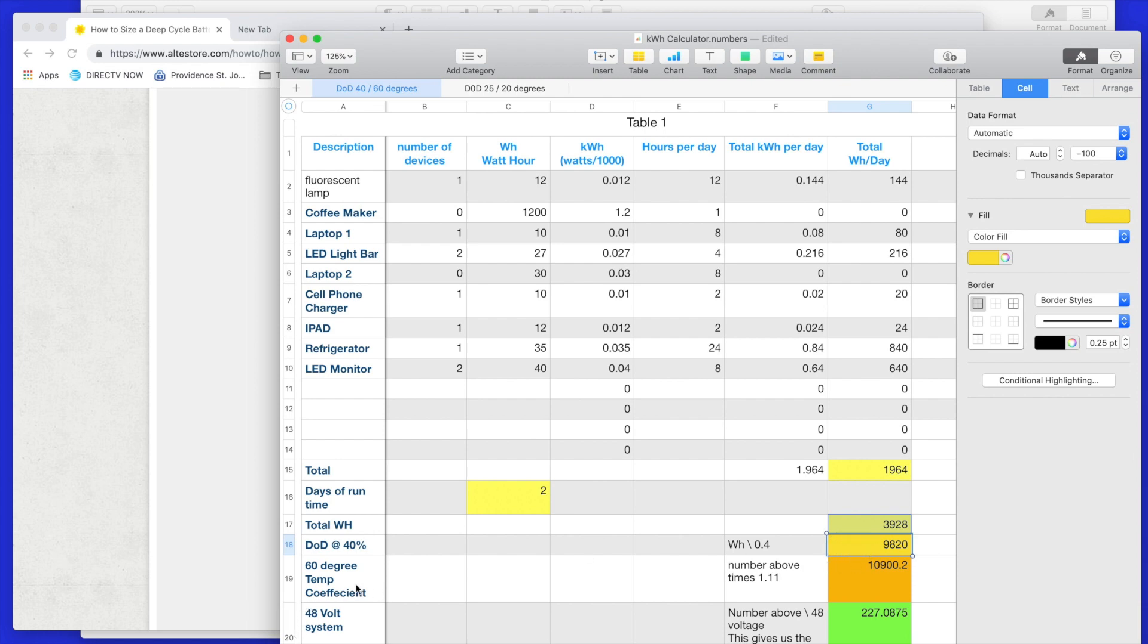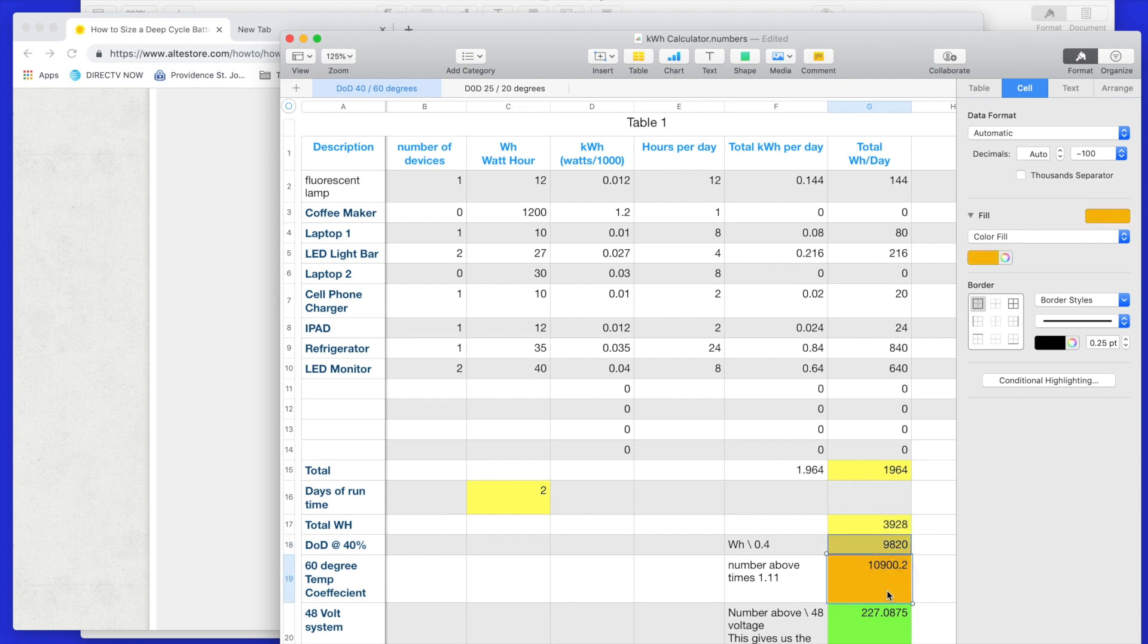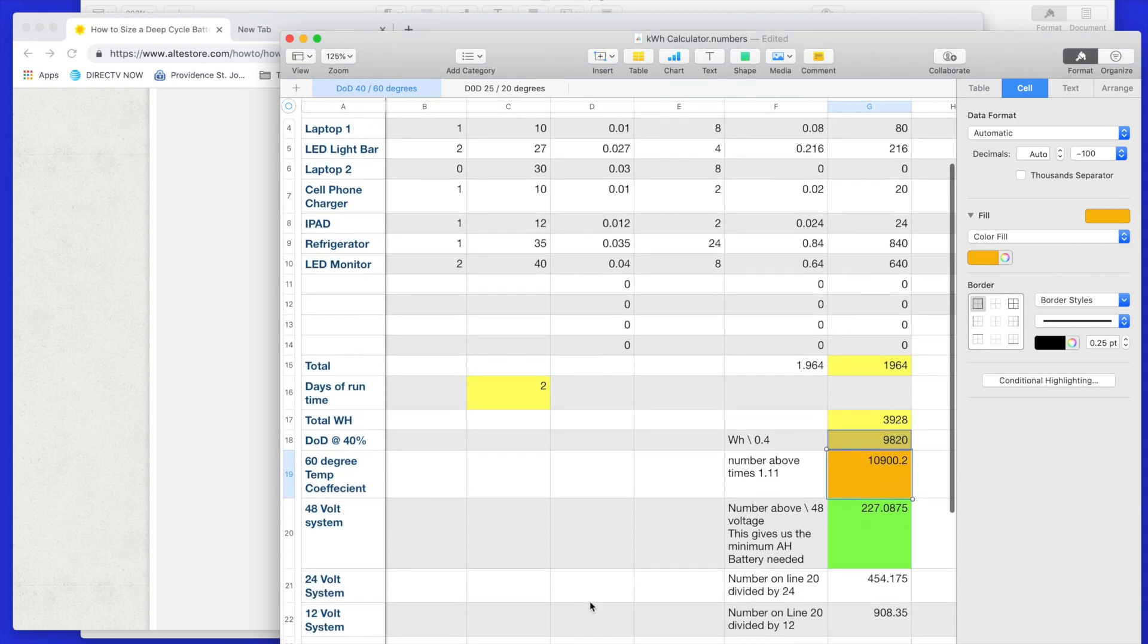Now we have a temperature coefficient. The battery is like 68 degrees, but at a 60 degree temp, it's at 1.1. If it was 30 degrees, it would be 1.4, I believe. Anyway, that's going to increase this number. It's going to go up substantially because you're going to take this number times the coefficient, which in this case, at 60 degrees, is going to be 1.1. It gives us that number right there.